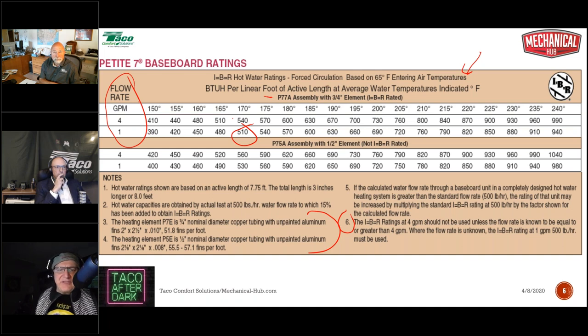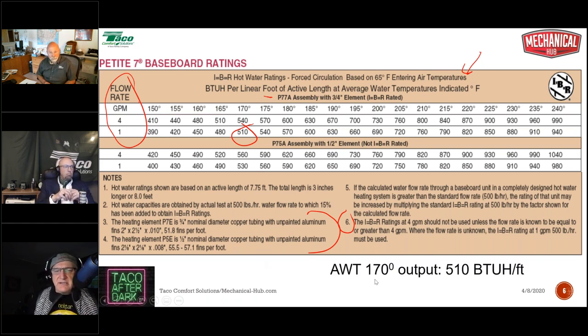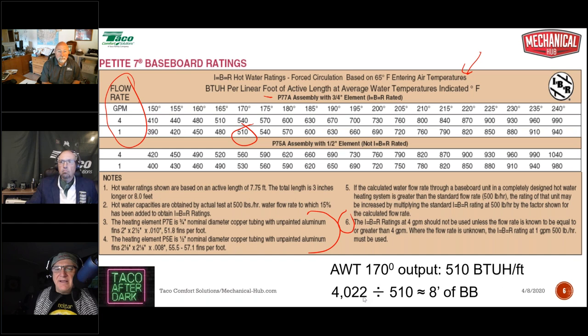How do we figure out how many feet? Well, we all know how to do that. We divide the heat load, 4,022 BTUs, by the amount of BTUs per foot at the water temperature that we're running. In this case, we're running 180 with an average of 170. All right, so we take a look at that. We have 170 average water temperature, and the output is 510 BTUs per foot. So 4,022 divided by 510 BTUs per foot. For this room, we're looking at about 8 feet of baseboard.